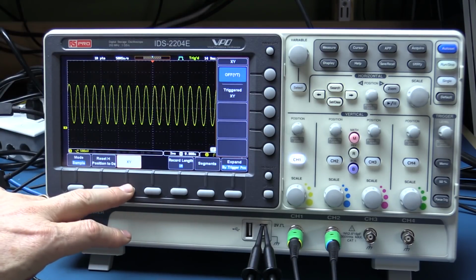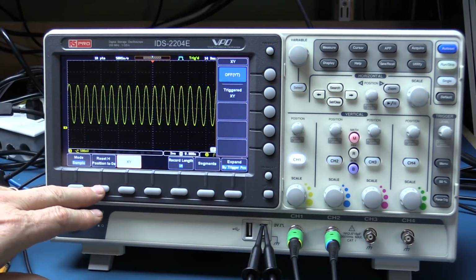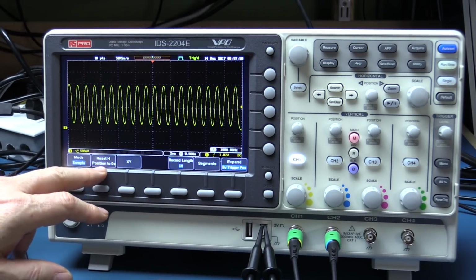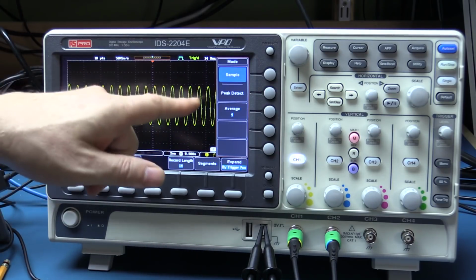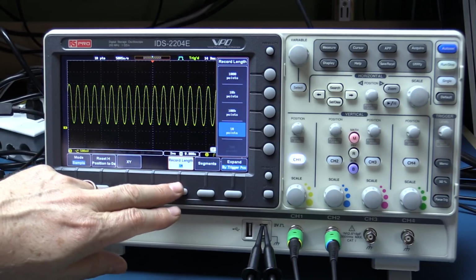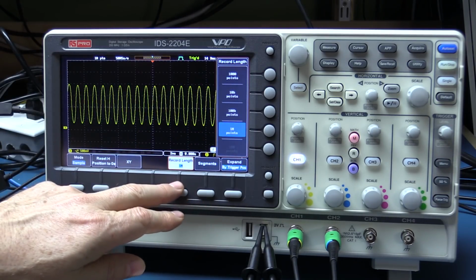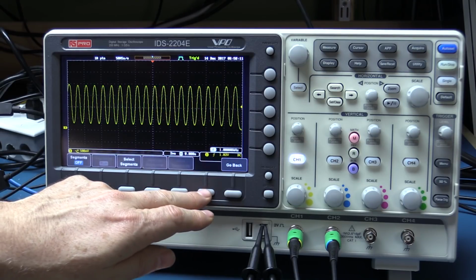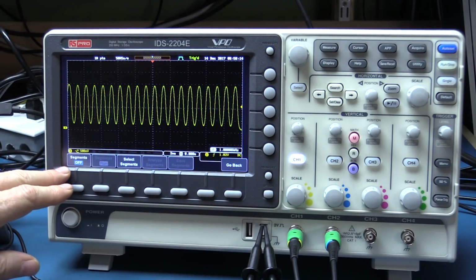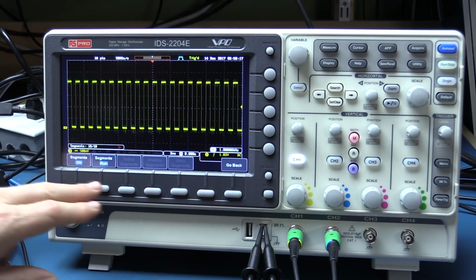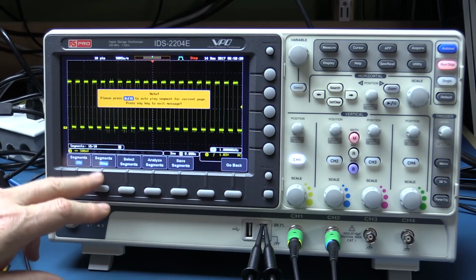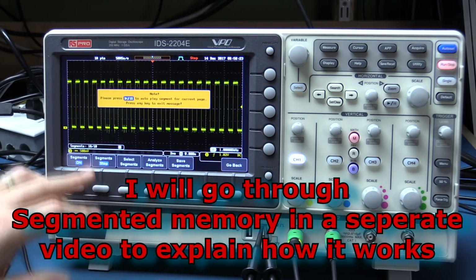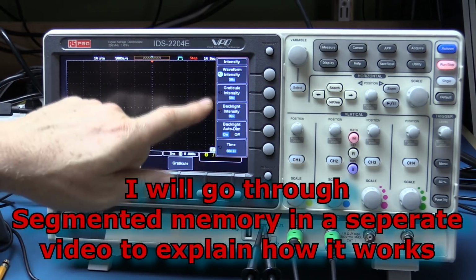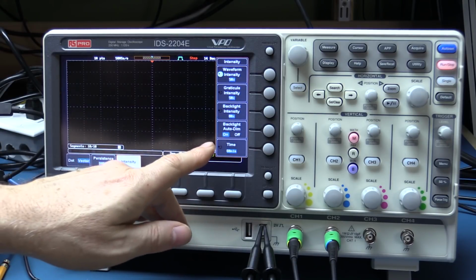You've got XY mode, on or off. You've got reset horizontal position to 0. Sample mode, sample, peak detect, averaging, and the ability to change your record length. The other bit here is where you get the segmented memory from. We can turn segmented memory on, and we can run the segmented memory, which is putting it into buffers. By default, I think we've got 10 segmented memories, but you can change that. Intensity, so you can change the waveform intensity, the graticule intensity, the backlight, and auto dim after 60 minutes.